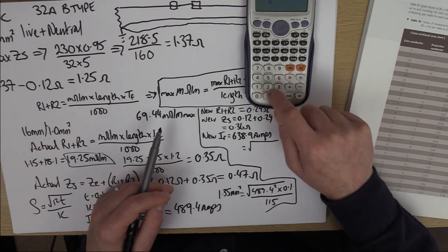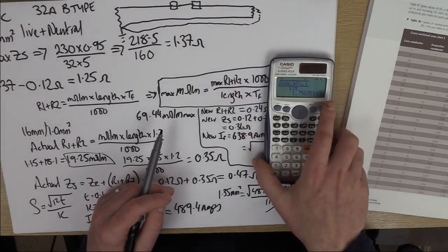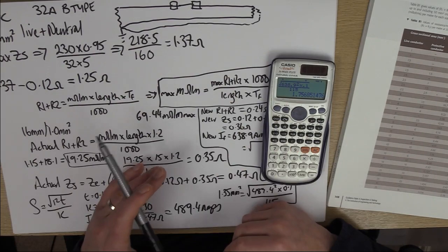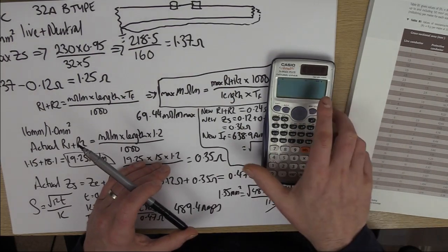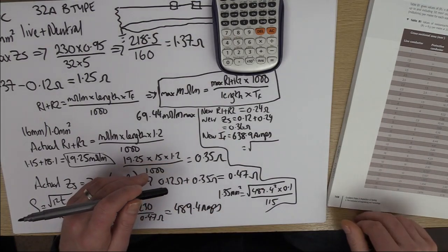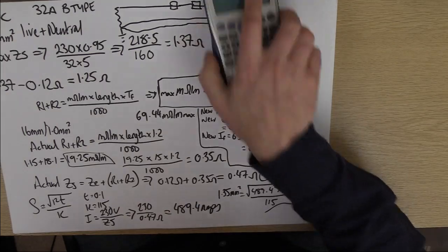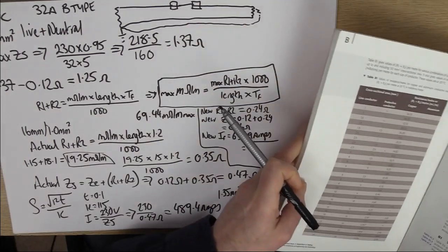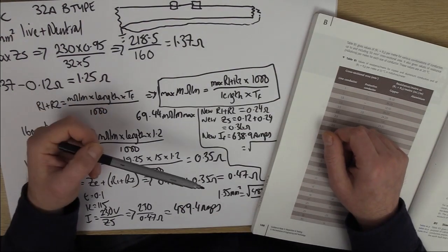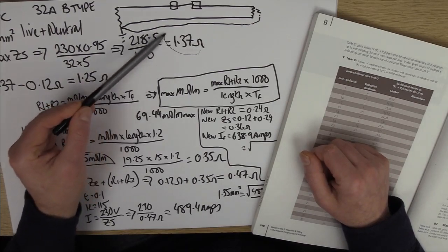638.9 squared times 0.1 over 115. So now it's saying minimum's 1.75, so the 1.5 doesn't work. Oh no. So should we just jump to maybe a more sensible kind of option? And this is a great example of where the ZS might comply, but your adiabatic doesn't. So you can't just go by this all the time.